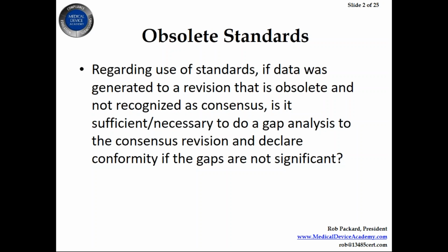Now, unlike the European Union, where you have to maintain your testing to the current version of the standard or the state of the art, the US FDA doesn't require that. Once you have a product cleared and it's safe and effective, they don't require you to continue to update your testing unless you make a change to the device. So if you don't make a change, you don't have to do any new testing. That's quite different from what the Europeans are requiring, where they require you to maintain the state of the art. So it's really important that you not just check what is the current standard that's recognized by the FDA, but also make sure that's the most current standard, period.